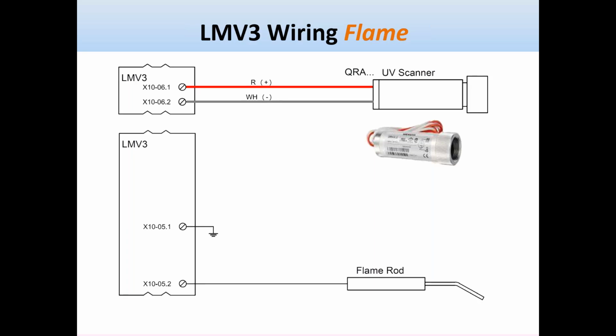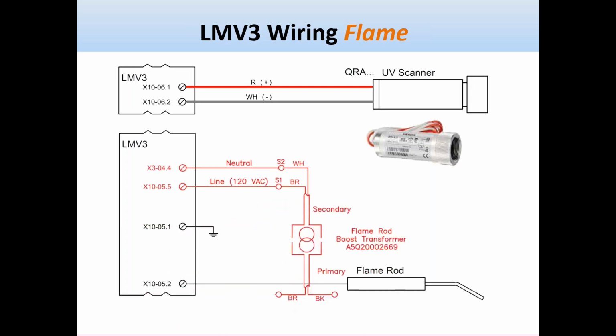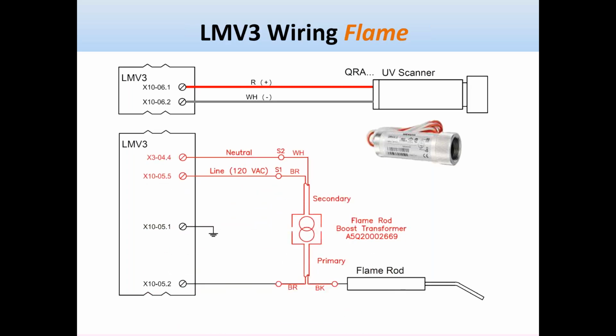The flame rod has a voltage on it that goes into the flame, and then you see the ground connection. The higher the voltage on the flame rod, the easier it is to detect the signal. Siemens provides an optional flame rod boost transformer. This takes line voltage off the LMV3 and provides about double the voltage to the flame rod so that the flame rod can pick up the signal. Again, this is an optional transformer that can be added to a flame rod application when you want to elevate the voltage on the flame rod.